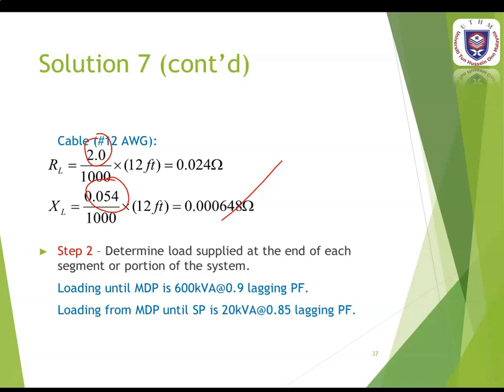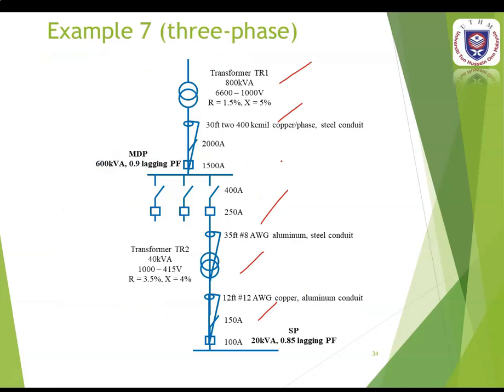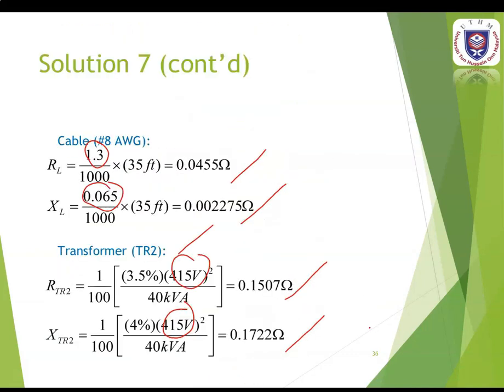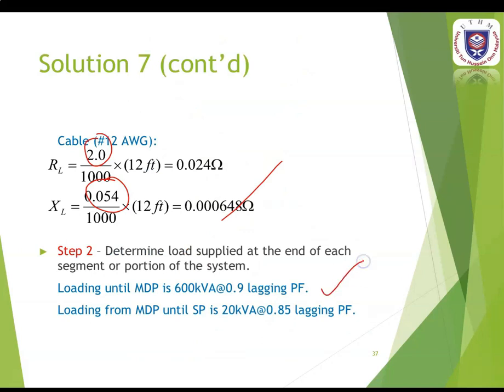After identifying all system impedances, the next step is to determine the load supply at the end of each segment. At the end of the main distribution panel is load 1 at 600 kVA with 0.9 lagging power factor. At the end of the service panel is load 2 at 20 kVA with 0.85 lagging power factor.